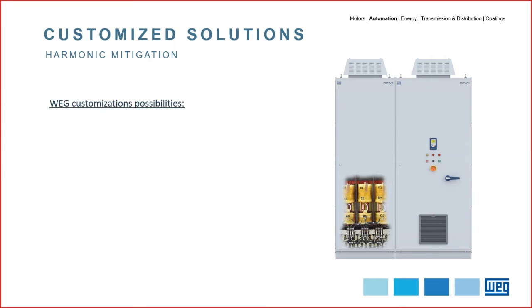And what are the WEG customization possibilities for harmonic mitigation? Let's start with a multiple-pulse configuration of the VSD panel. In these cases, the VSD panel may be equipped with a multiple-pulse rectifier of 12 or 18 pulses, and it's necessary to consider a phase-shifting transformer outside the VSD panel. An increase in the number of pulses of the input rectifier will reduce the harmonic content injected into the grid. This is a good option to be considered when the grid is available in medium voltage.